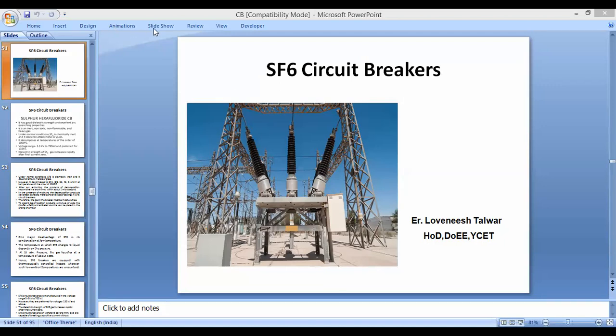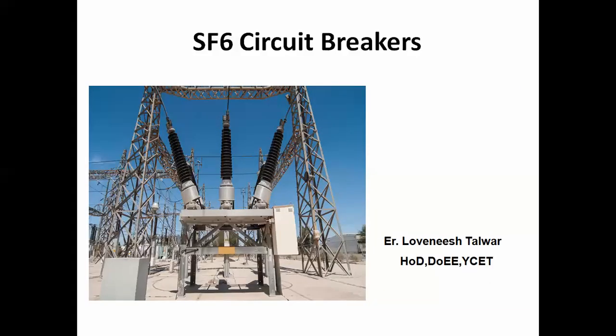And in the oil circuit breaker as well as in the air blast circuit breaker, you saw how the arc is generated within the circuit breaker, and when the arc is generated, you have to quench this arc in the minimum possible shortest time, because if this arc persists in the circuit breaker, it will increase the temperature of the system, as well as affect the circuit breaker itself.